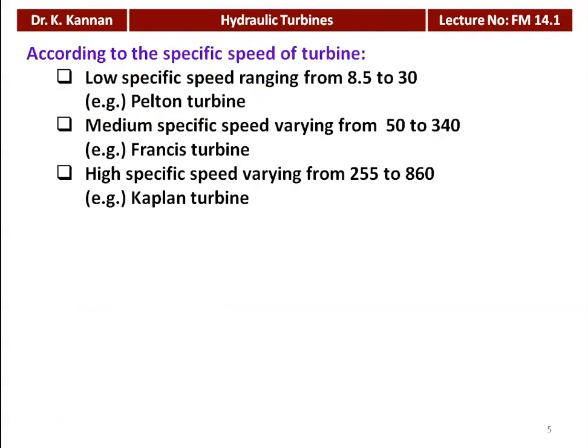According to the specific speed of the turbine — specific speed is an important design parameter. Low specific speed ranging from 8.5 to 30: we use the Pelton turbine. Medium specific speed varying from 50 to 340: the Francis turbine is the example. High specific speed varying from 255 to 860: the Kaplan turbine is the example. You have to remember these numbers, as competitive examinations often ask you to match the specific speed range with the type of turbine.